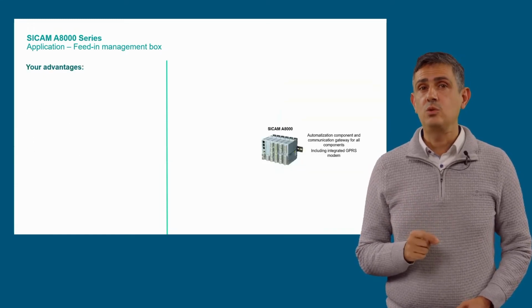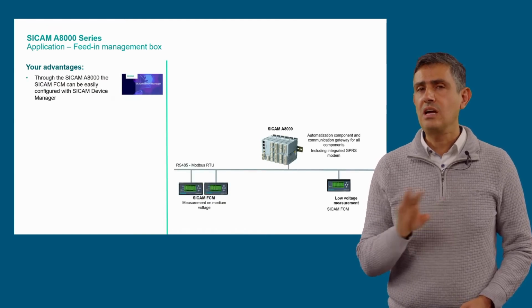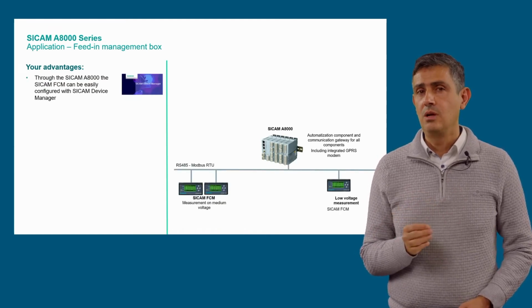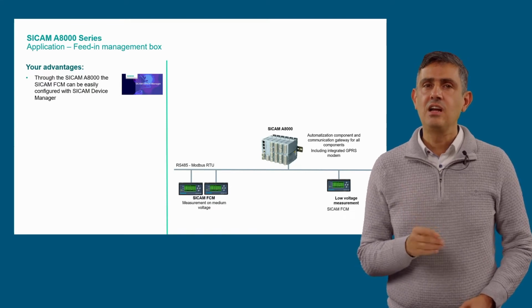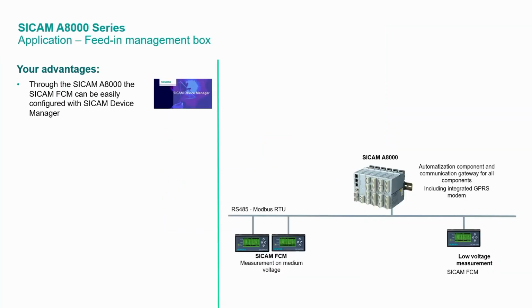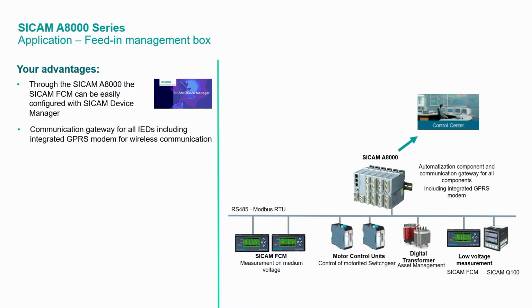Your advantages with this solution: the SICAM FCM modules don't have to be configured individually through a separate tool, but they can be configured with SICAM Device Manager through the SICAM A8000 via Modbus. So you have central management of all the configuration parameters. You just set the parameters in SICAM Device Manager and you are ready. The SICAM A8000 acts as a gateway to get all the information from the included IEDs seamlessly. So all information can be provided to the upper level through various communication protocols, such as IEC 104 or DNP3, also wirelessly with the integrated GPRS modem.